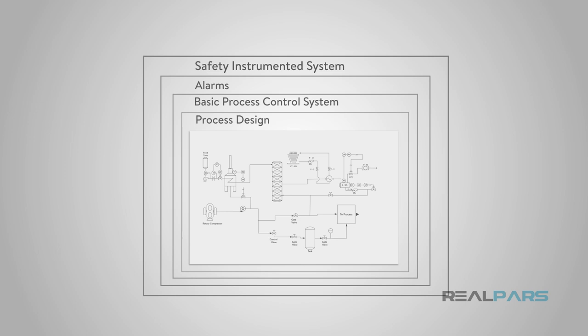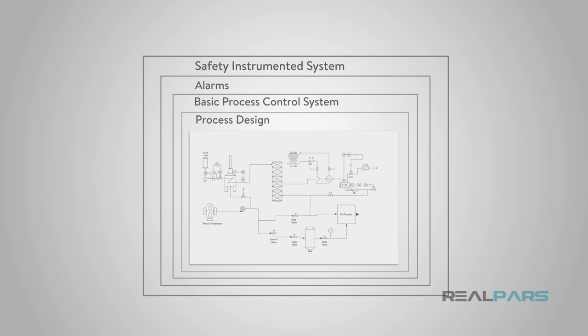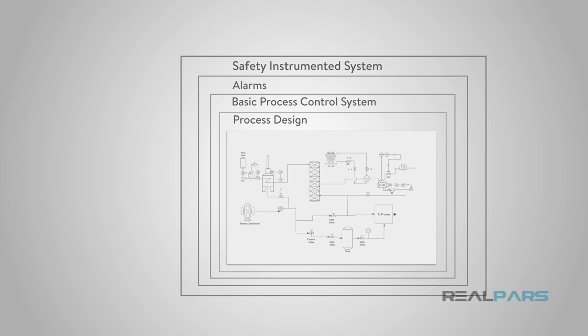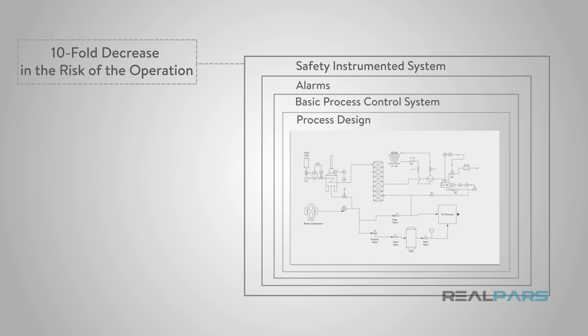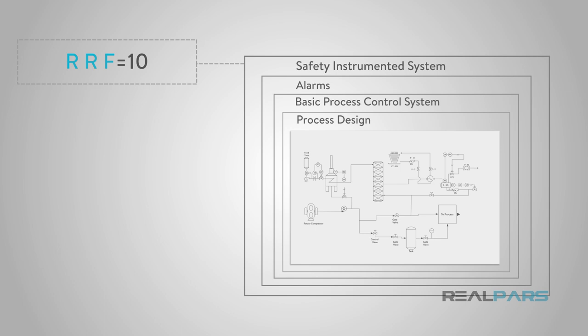The safety instrumented system, or SIS, represents an additional layer of protection above the first three layers discussed previously. This layer should provide at least a ten-fold decrease in the risk of the operation, which can be called a risk reduction factor of equal to or greater than ten.